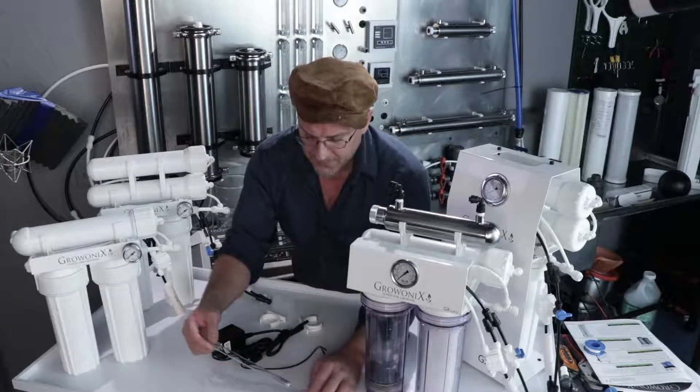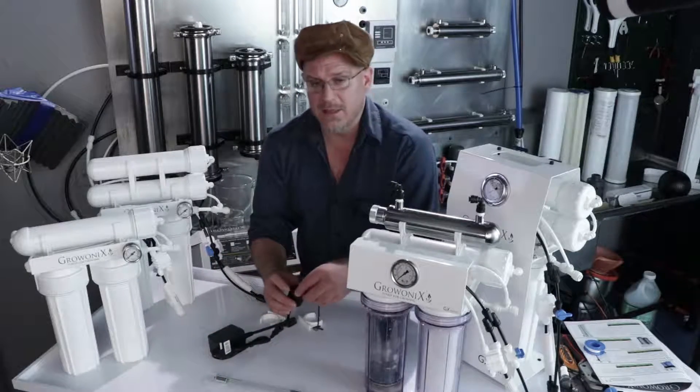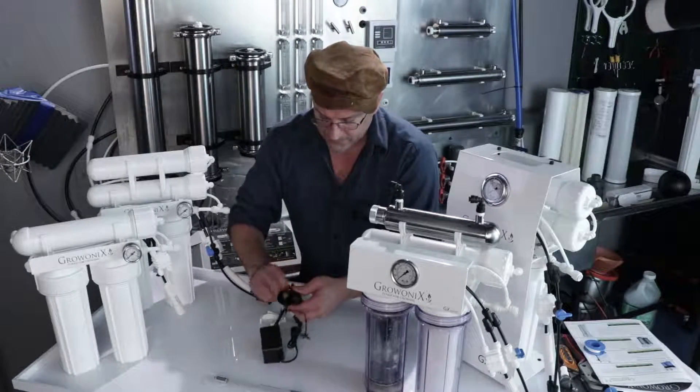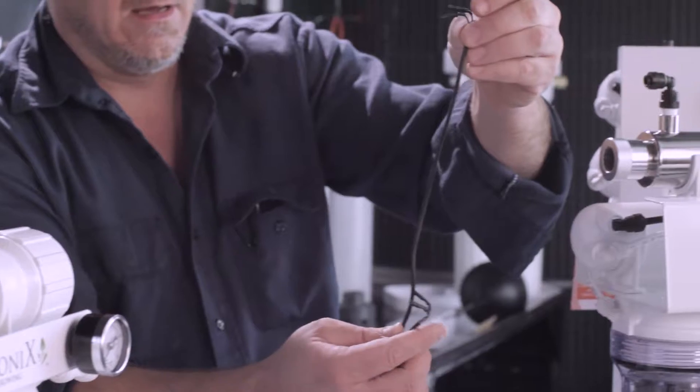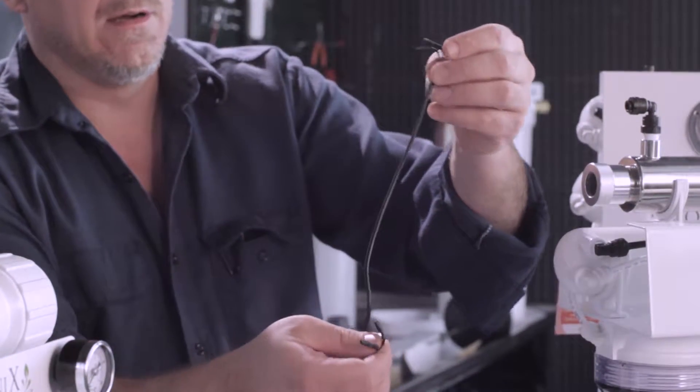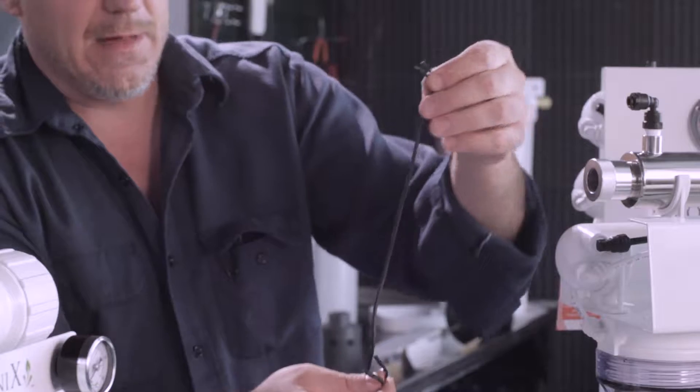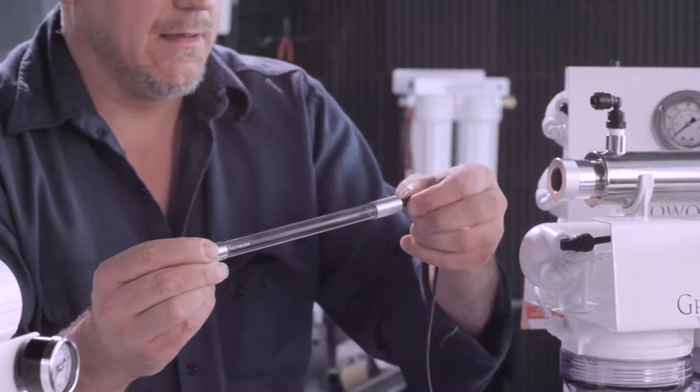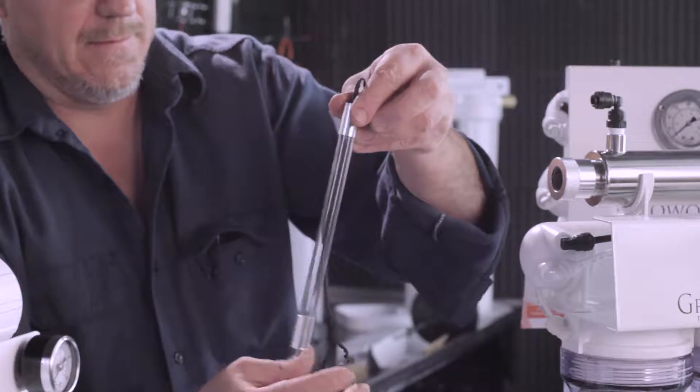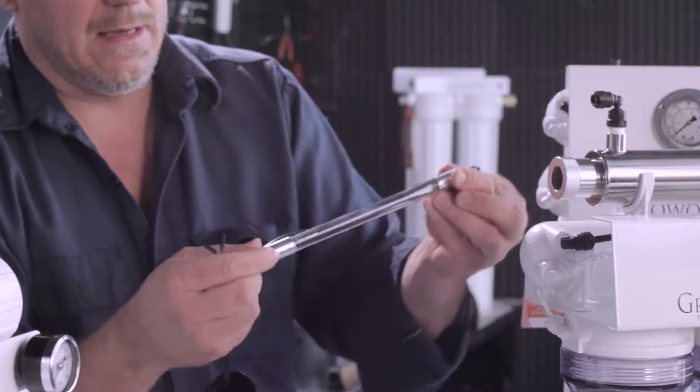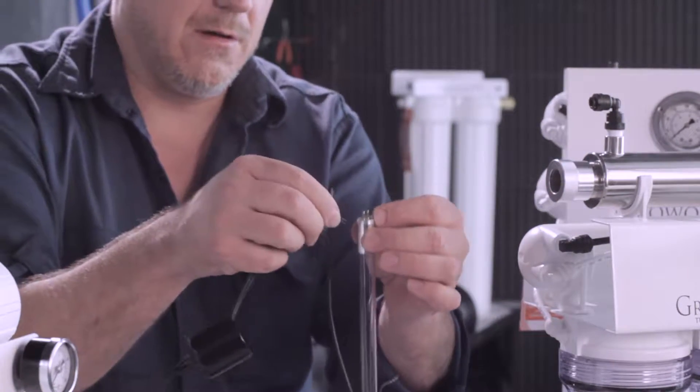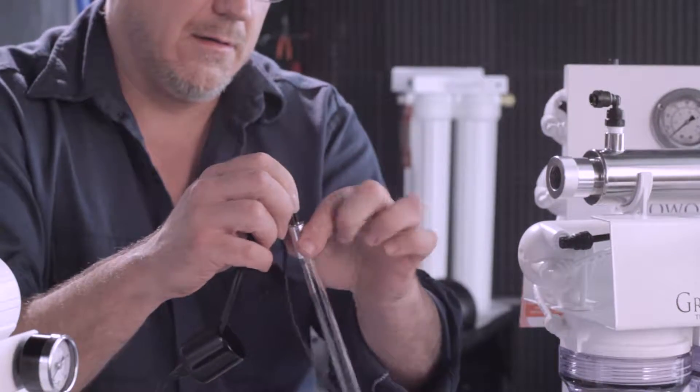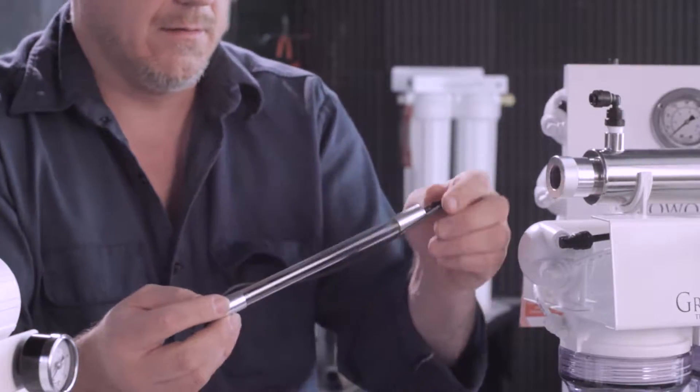So, unlike the bigger UVs, we have to wire up the ballast on both ends before we insert the bulb into the stainless housing. So, the wiring harness for the bulb has connection points down here, the brown wires. And two connection points above, the black wires. Simply take the bulb, don't touch the glass. And connect the black wires like that. And then, you can take the other end of the bulb and connect the brown wires. They go on really easy. They're just push connect fittings.